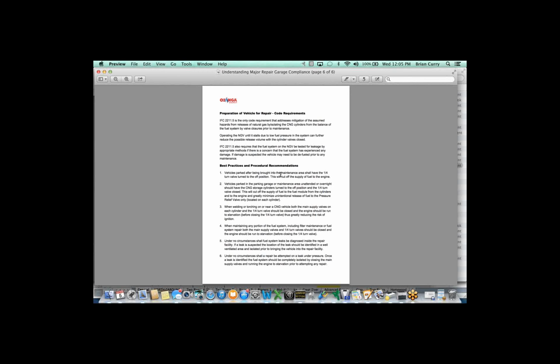There's usually an access hole for the tanks, whether they're mounted behind the cab, on the frame saddle, or on top of the truck like a garbage truck. Typically, we would protect those holes with a fire blanket. And if anybody was going to be doing any welding or torching on that truck, we would assign a fire watch that would keep an eye on the area to make sure that there are no smoldering flames or chances of damaging the tanks. As everyone probably knows, if they've worked around carbon fiber tanks, whether Type 3 or Type 4, any damage whatsoever as a result of fire is an automatic disqualifier for that tank, and you've got to replace it.